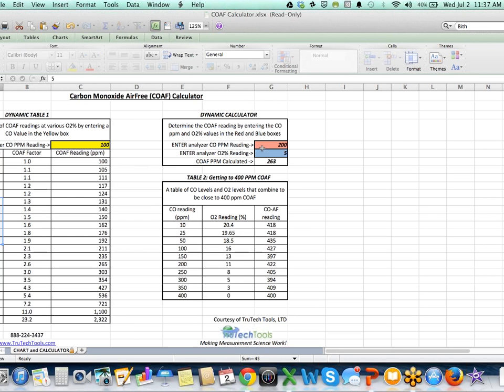Another way to look at it, this is a dynamic calculator that just produces results. You need to give it two inputs. So this would be like you're inside the brain of the combustion analyzer, and you're giving it 100 parts per million CO coming from the CO sensor, and then 8% oxygen coming from the oxygen sensor. The CO air-free calculation that would pop up on that line on your screen would be 162. So this is a way of figuring out how these things work inside the combustion analyzer.